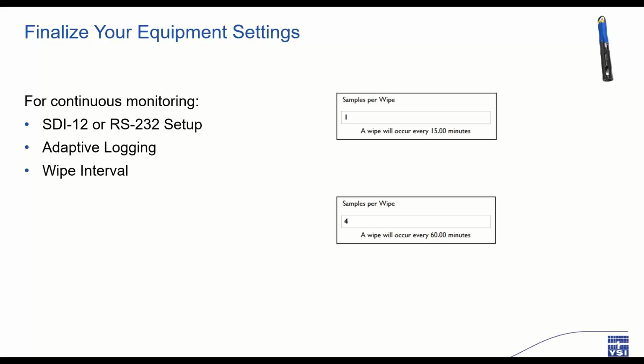Finally, you'll want to set up an appropriate wipe interval based on the power at the site. If you are running the sonde solely on internal battery power, you may want to wipe less frequently, whereas if you're connected to a gauge with a solar panel and external battery, you may want to run the wipe cycle before every sample is collected.